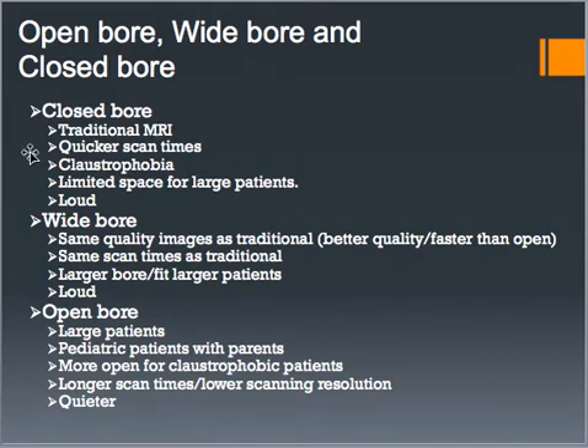So to break them down into sections, the closed bore is the traditional MRI scanner. You have a quicker scan time than open bore. But the problem with that is it can cause claustrophobia, there's limited space for larger patients, and they can be loud. The open bore is great for larger patients or pediatric patients. A lot of times with pediatric patients, instead of sedating them, they'll have the patient's parents stay right there with them inside of the scanner. They're not being scanned themselves, but it gives the pediatric patient a little bit of comfort. So they're more open for claustrophobic patients. The problem is, because they're a weaker magnet, they have a longer scan time and lower scanning resolution, but they are quieter.